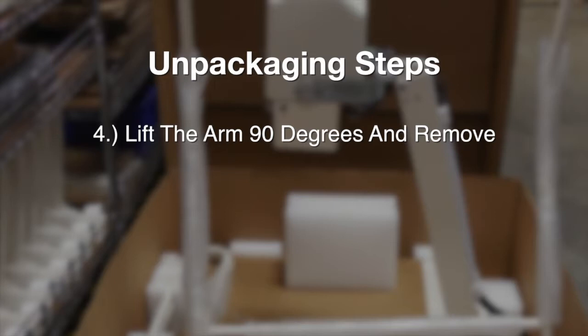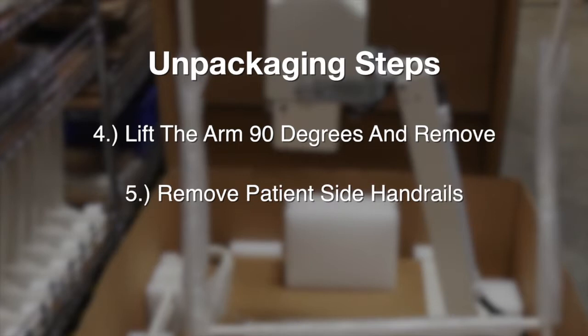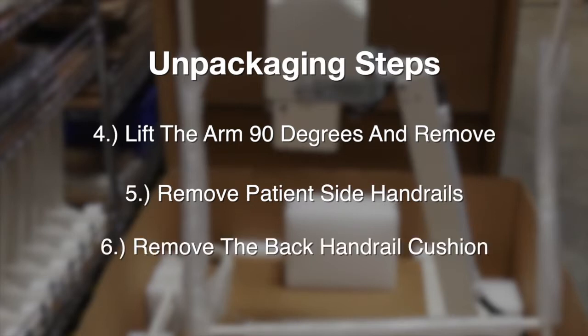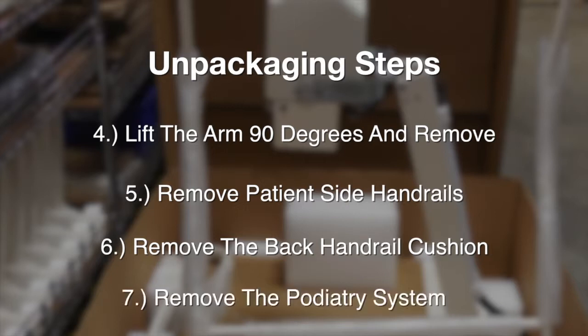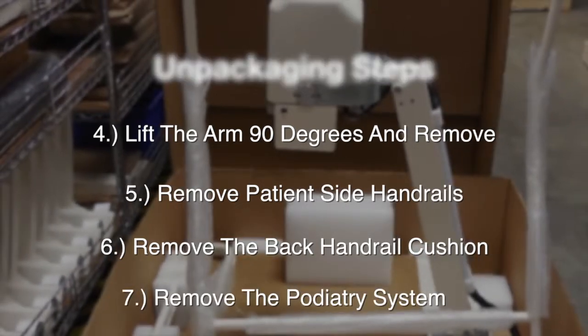Keep in mind the podiatry support base contains a spring-loaded arm with 500 pounds of force. Never remove the x-ray head while the arm is in a position other than the 90 degrees vertical. Next, remove the patient side handrails from the cushions. The back handrail cushion should then be removed and set aside. You want to then remove the podiatry system from the base and set aside.